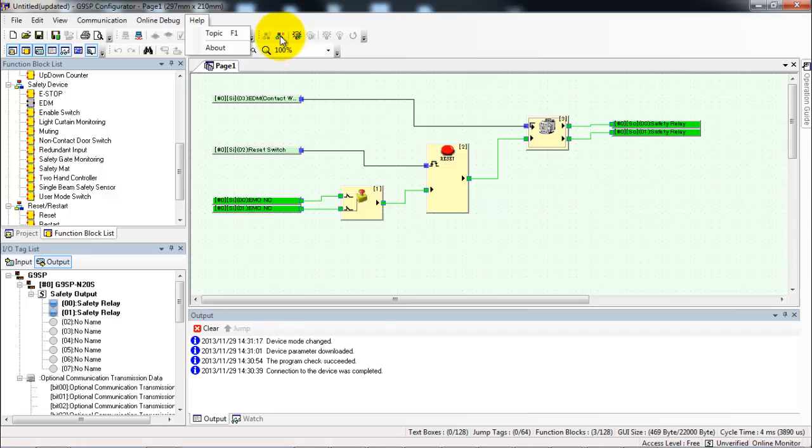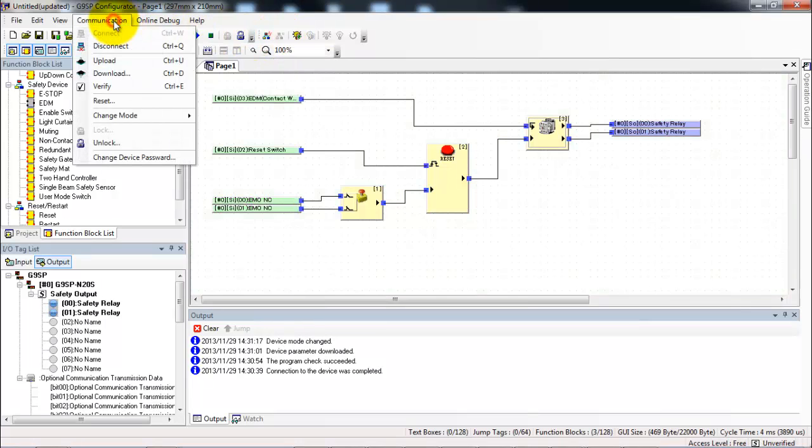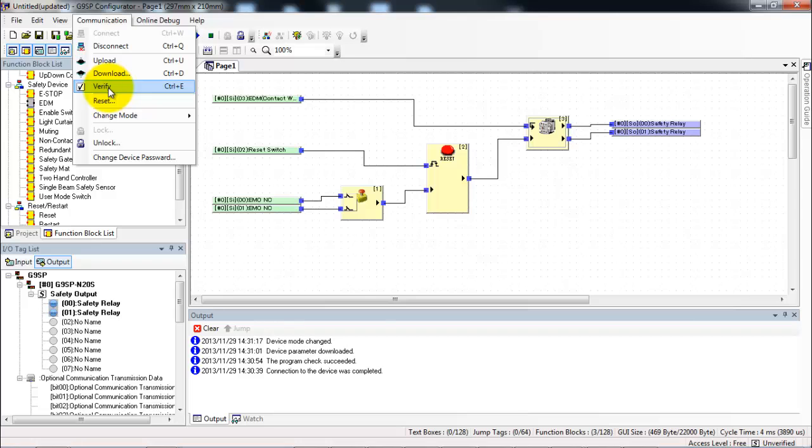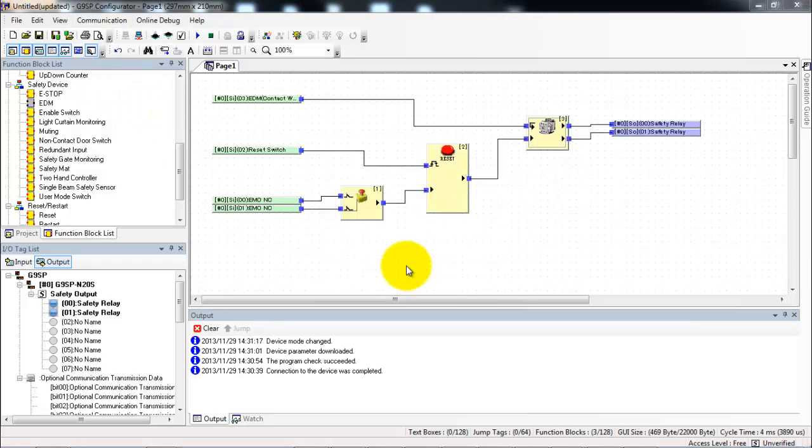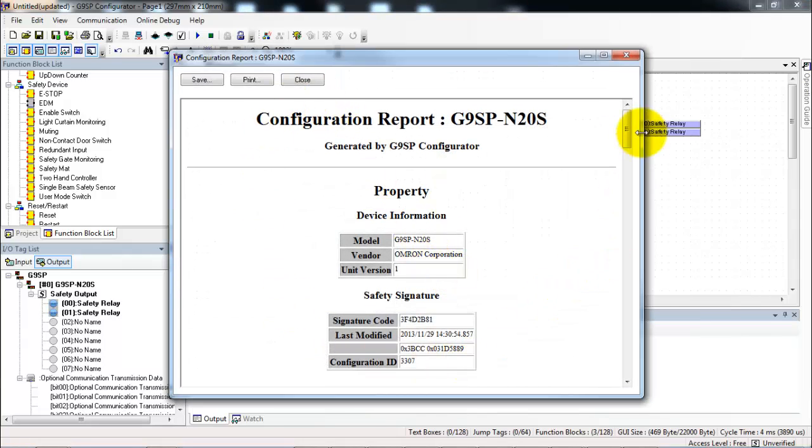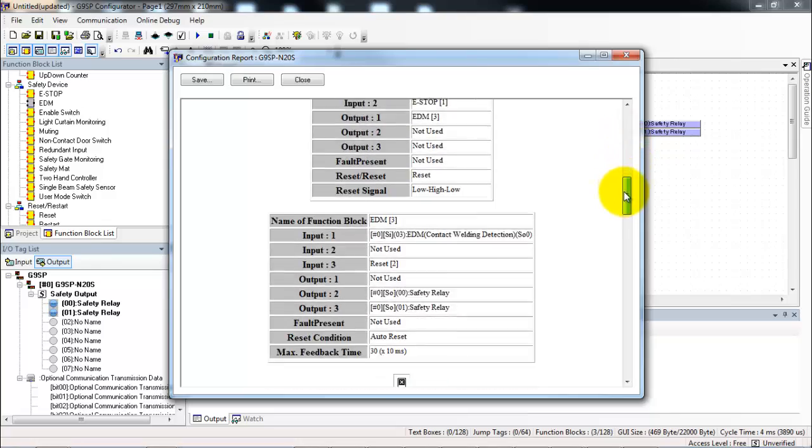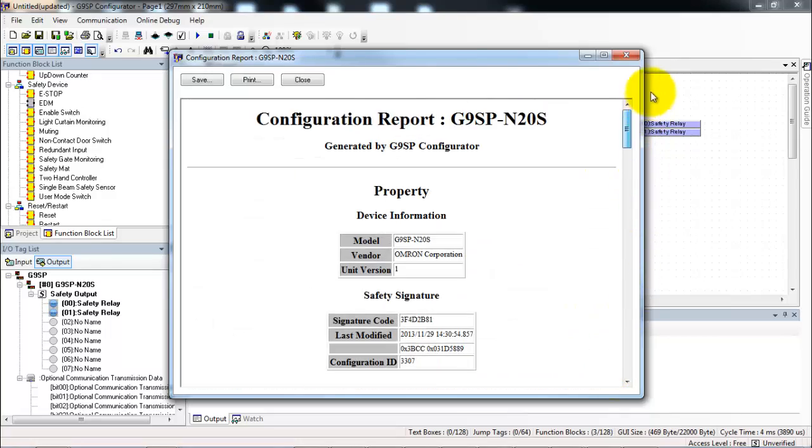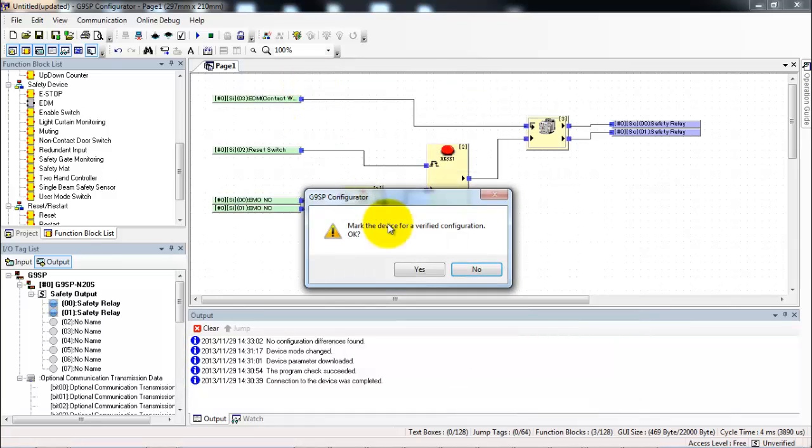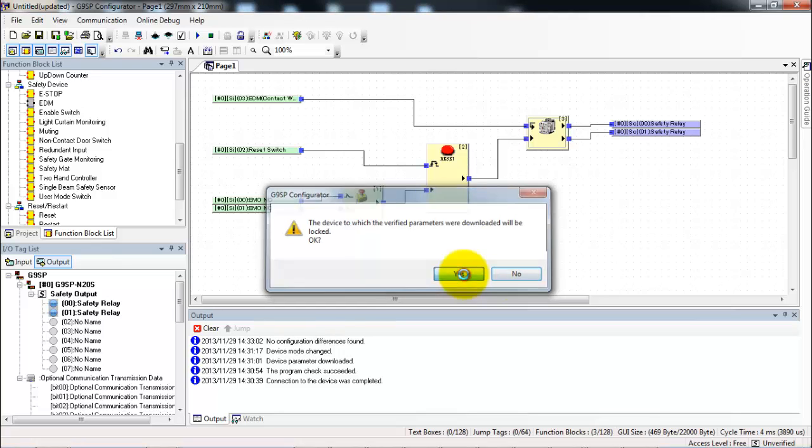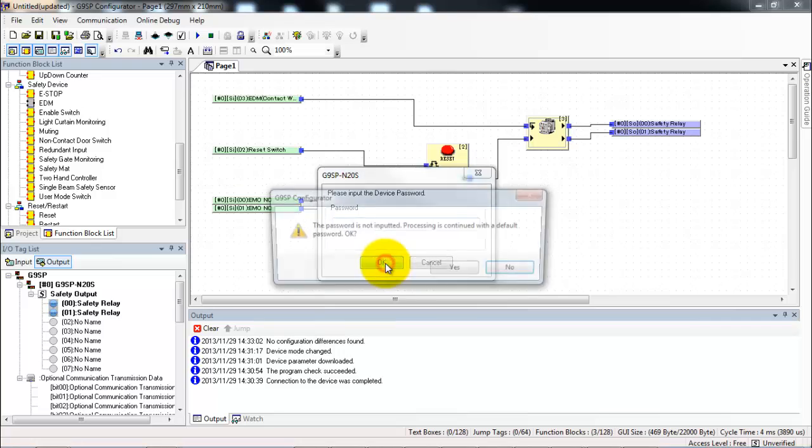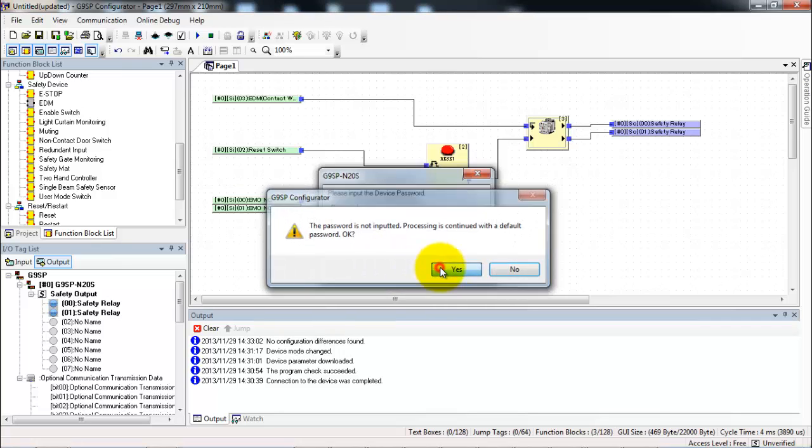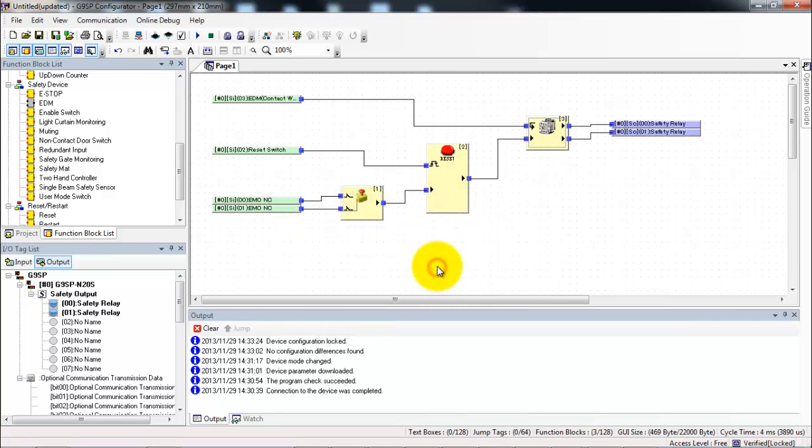So to make this happen first I need to shut off the monitoring. Next I go to communication and verify. This will check that what's in the controller now exactly matches what's on my computer screen. It then generates a configuration report that I can use to verify the configuration. And lastly it asks me if I want to lock the device and I will say yes. And of course a password. Generally the password is always blank but I recommend if you're doing one in the field that you actually do put one in.